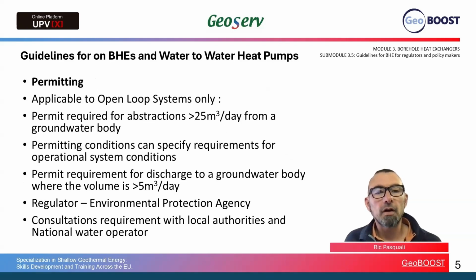In terms of permitting, as explained earlier, this is only applicable to open-loop systems. Permits that are required for water-to-water heat pumps require that a system applies for a permit where groundwater abstraction from an aquifer or a groundwater body is greater than 25 cubic meters per day.